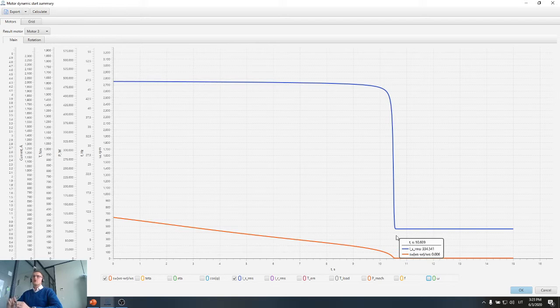So our protection devices should be capable of withstanding this kind of current for at least 10 seconds, because otherwise, if we set our protection devices below the motor starting curve, they might trip during motor starting. Here is the slip curve, by the way, this orange one, which shows that at this point the motor reached its nominal speed and the slip is very low, so basically the motor is started here.